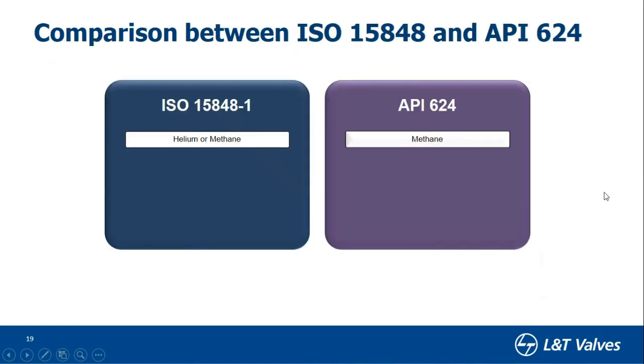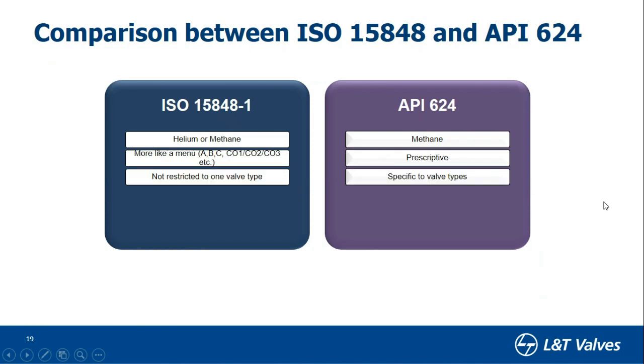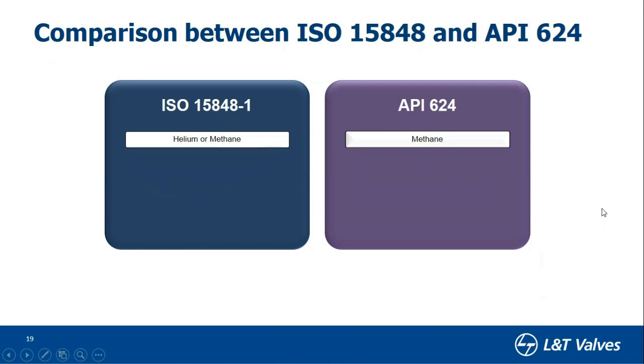Now let's compare the two widely specified standards: ISO 15848 Part 1 (qualification standard) and API 624. The test media for ISO is helium or methane, whereas for API it is only methane. API has fixed, prescriptive standard values — for example, you must do a specified number of cycles and the leakage level is 500 ppm. ISO, on the other hand, has different categories of leakage — Class A, Class B, Class C — and cycle categories CO1 (1000 cycles), CO2 (higher cycles), making it more menu-driven.